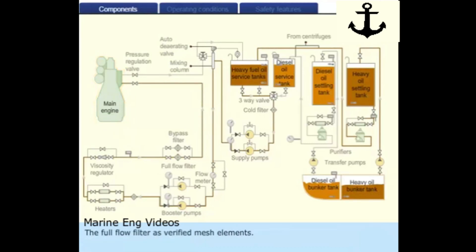The full flow filter has very fine mesh elements. A bypass filter is provided to clean the full flow filter during operation. The unused oil is returned either to the service tank or to the mixing column.